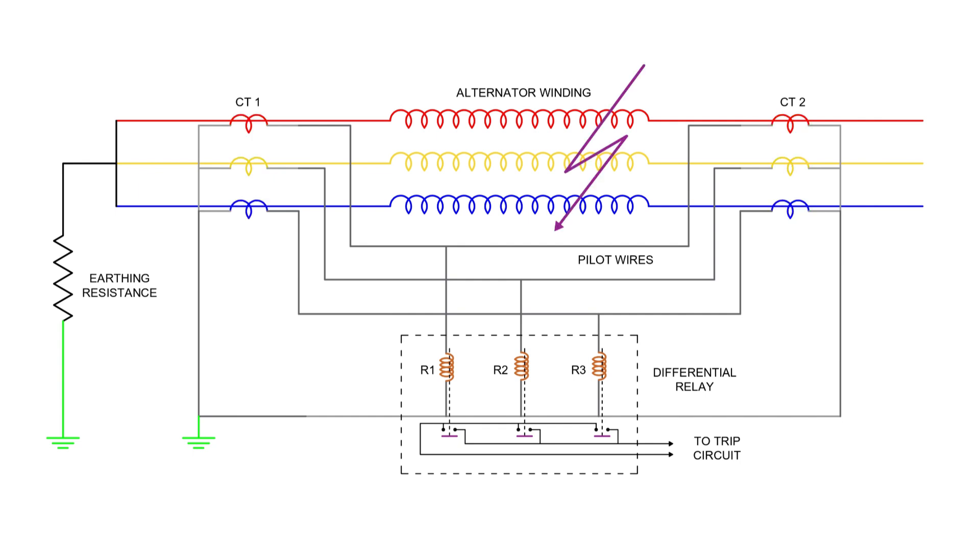But the moment a fault occurs, this symmetry is broken. The imbalance results in current flowing through the relay coil corresponding to the faulty phase. These are electromagnetic relays, designed to act instantaneously to trip the breaker and clear the fault as quickly as possible.